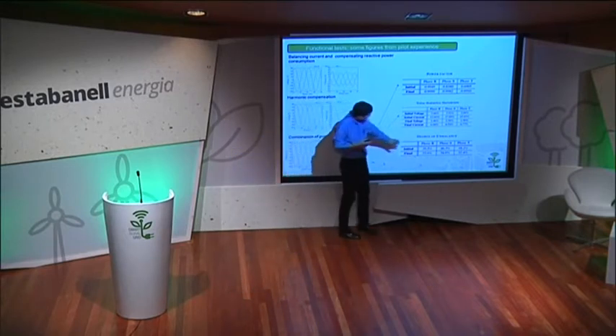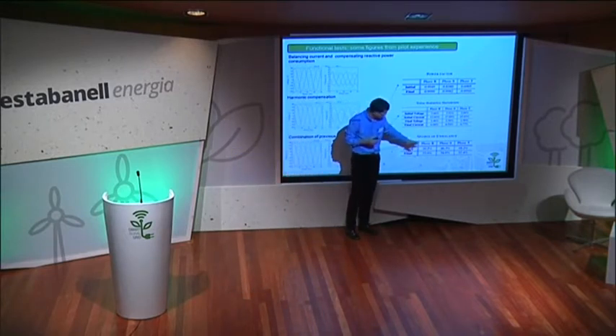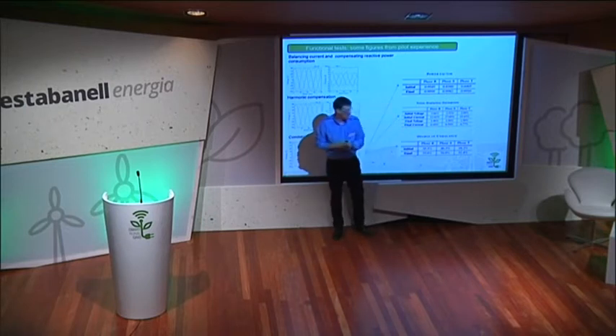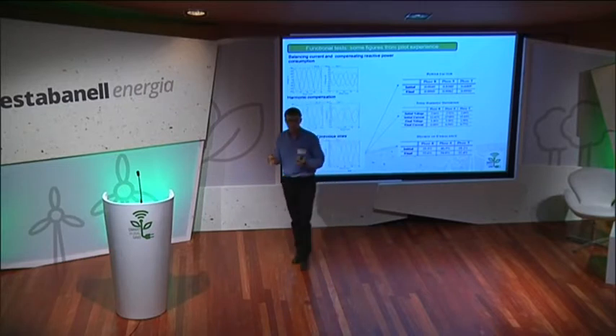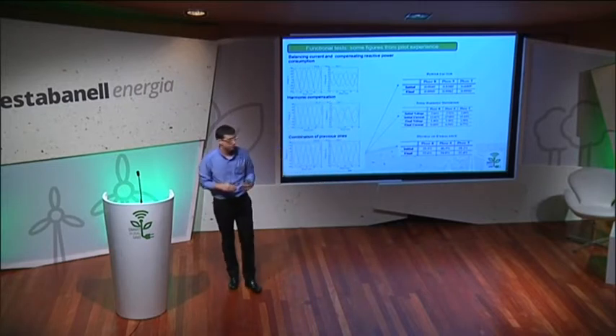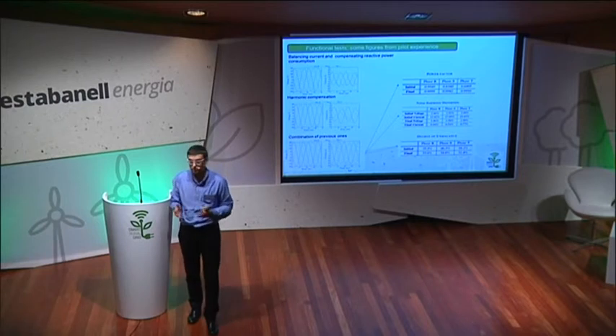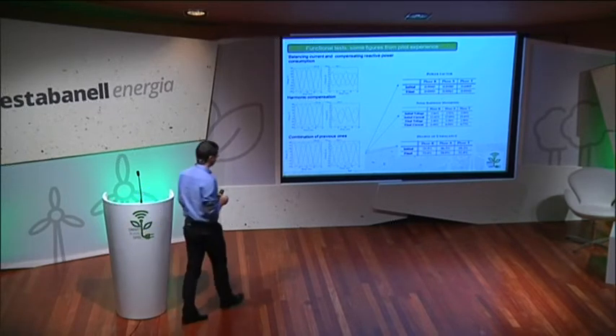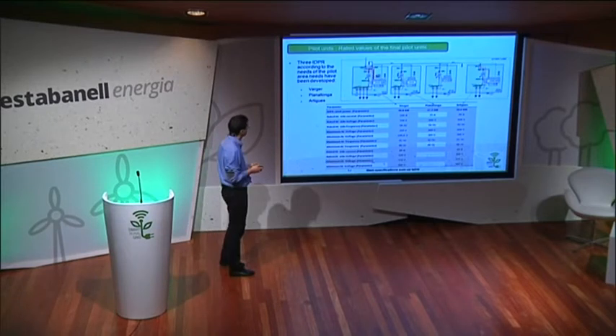And in terms of balancing, before the connection of the IDPR, we have one phase that is only contributing in terms of current about 80%, and after the connection, the system is totally balanced, and each phase is contributing with 1/3 of the total required power.